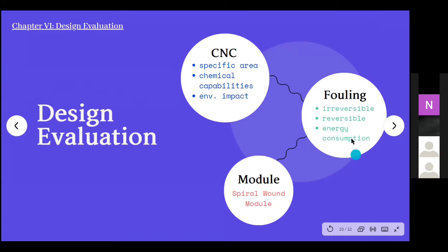Fouling may occur when suspended solids, microbes, and organic materials are trapped on the membrane surface, causing decreased permeate flux. Consequently, higher pressure than normal is needed to enhance the passage of the water through the membrane. Although CNC has high mechanical strength and rigidity, the extra pressure needed to solve these foulings will cause high energy consumption and reduction in membrane filtration area.